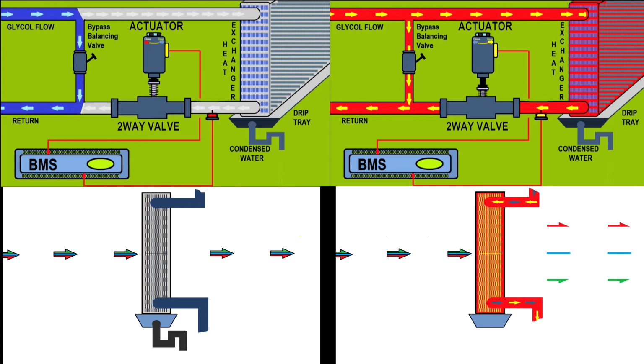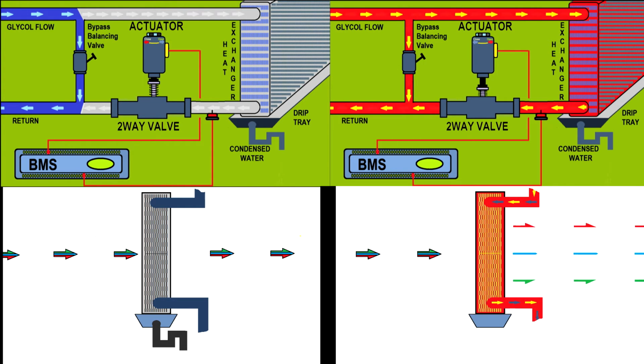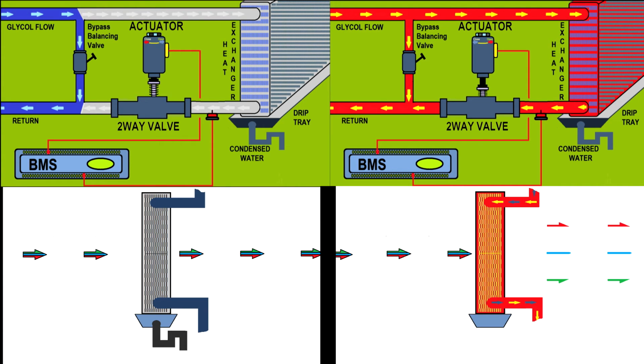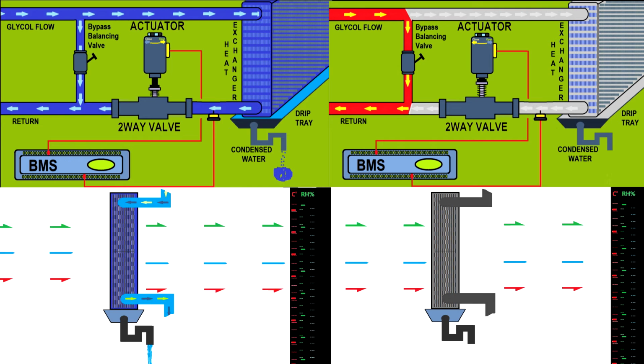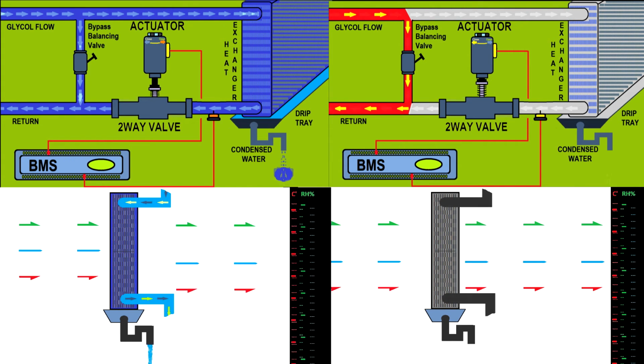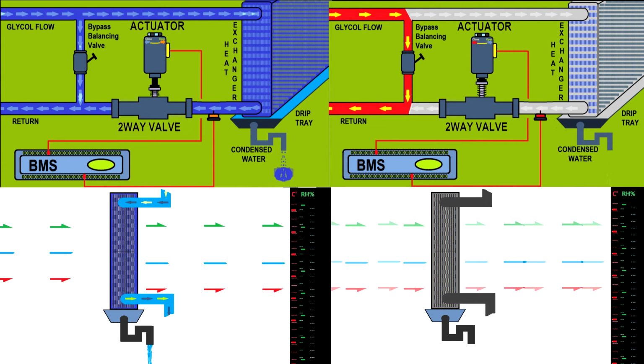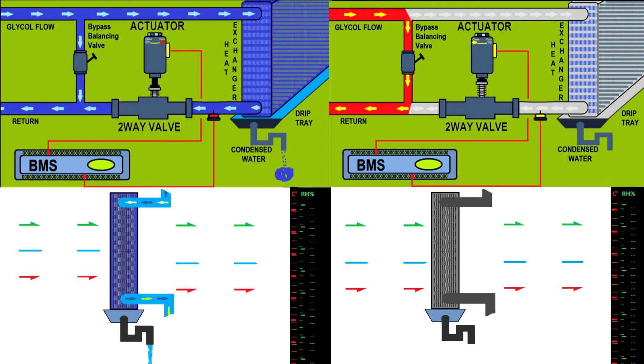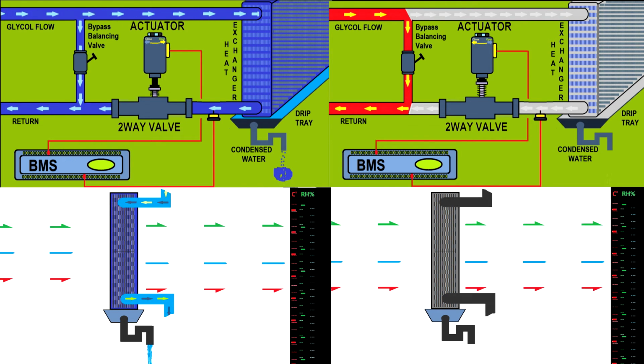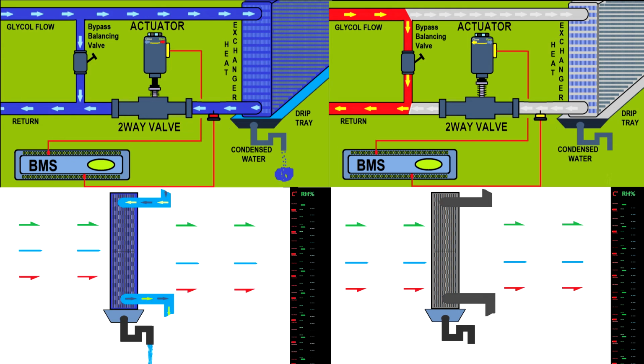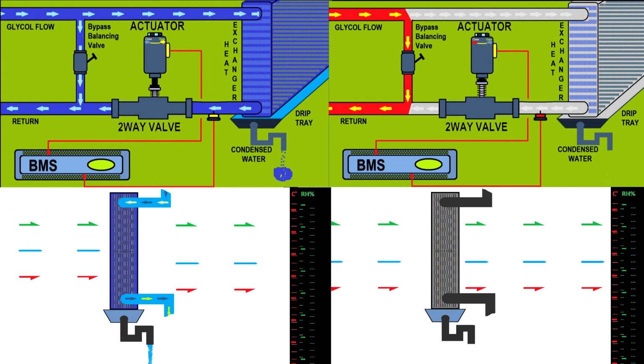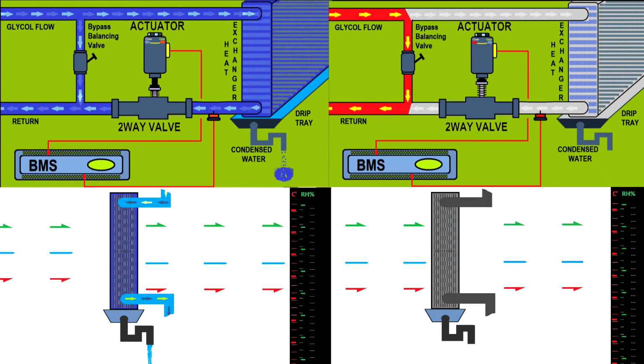If you heat the air, now you'll see on the right hand side the red line, which is the temperature, goes up. The relative humidity this time goes down. Absolute humidity stays, no modification. Now you run the coil on the left hand side below the dew point, and you'll see the blue line goes a little bit lower, which means you remove moisture. You can see the pipe below on the left hand side is removing moisture.